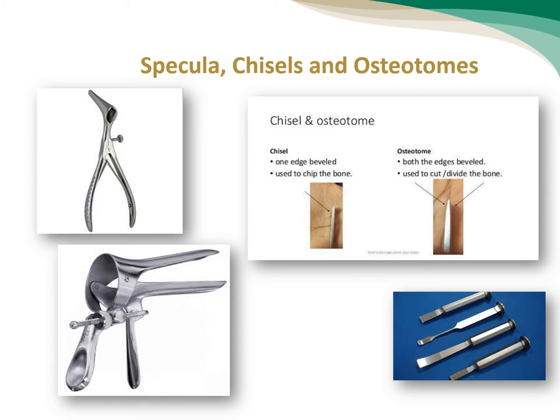The last three categories of reusable medical devices are the speculas, chisels, and osteotomes. We have here the nasal speculum. We have to check the screws and any debris or bioburden attached to the tip of it. Also, the vaginal speculum: we have to check whether any screws are loosened or debris is attached to it. And the last two things are the chisel and osteotome.